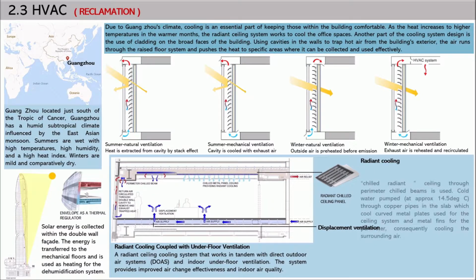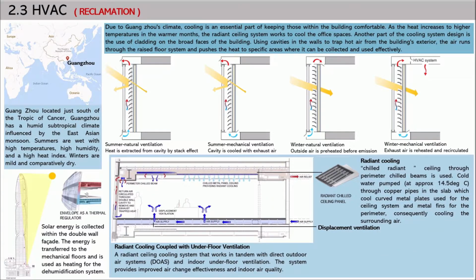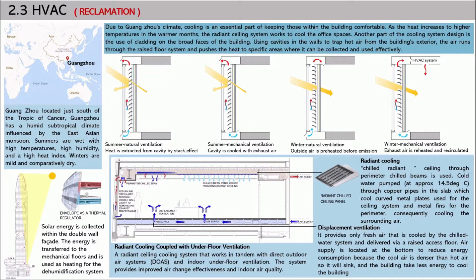For radiant cooling, chilled radiant ceiling through perimeter chilled beams is used. Cold water is pumped through copper pipes in the slab, cooling curved metal plates used for the ceiling system and metal fins for the perimeter, cooling the surrounding air. Air supply comes from displacement ventilation, providing fresh air cooled by the chill water system and delivered via a raised access floor. The air supply is located at the bottom to reduce energy consumption, because cool air is denser than hot air and sinks, so the building takes less energy to cool.